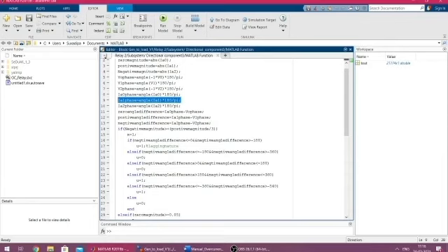Then we have used some if-else statements to define the relay trip logic. In case our angle difference comes out to be positive, that is 0 to 180 degrees, it will be called a reverse fault. In that case, the relay should not trip. So the output of this directional relay element will be given as binary 0.